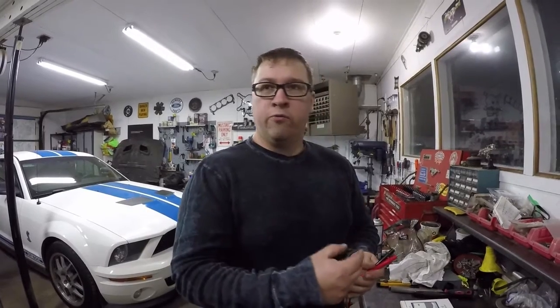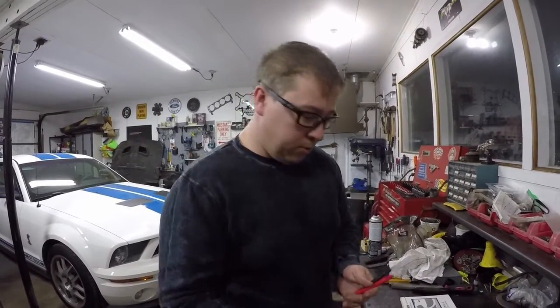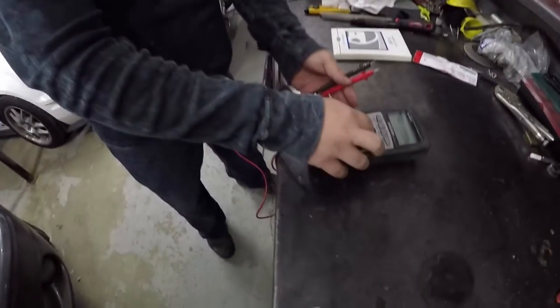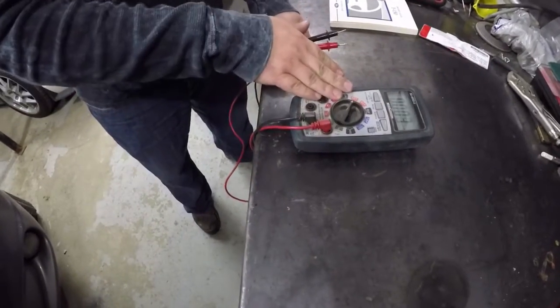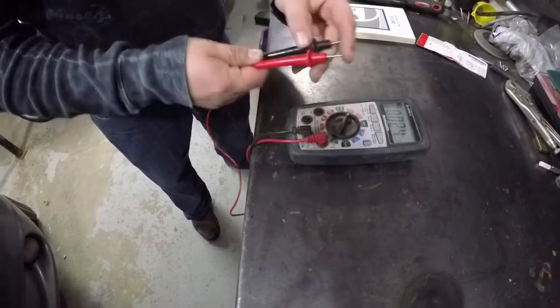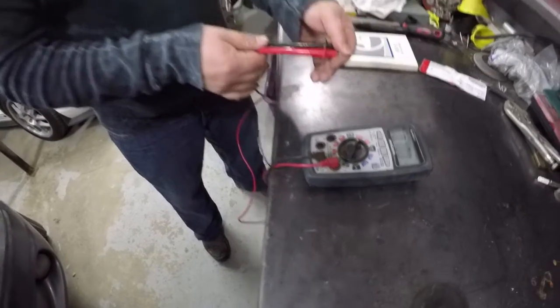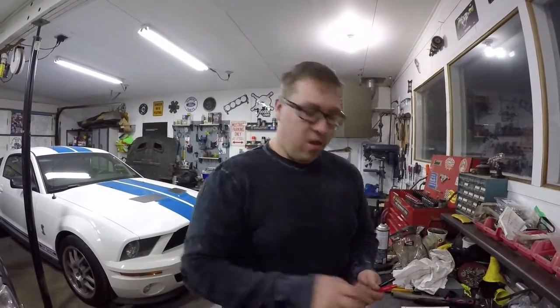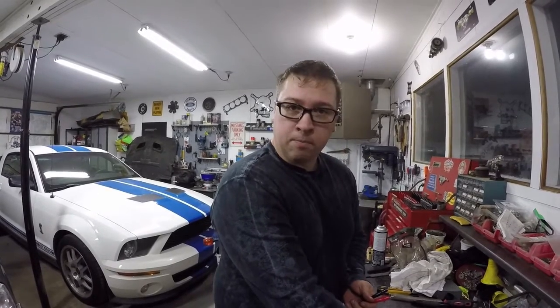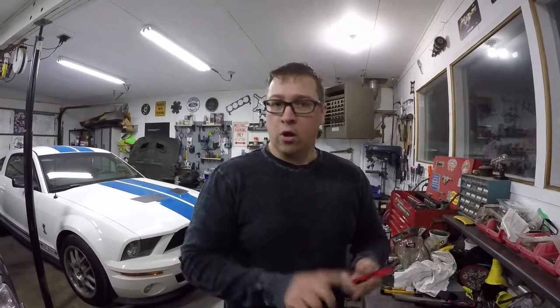And there's another way you can check beyond the fuses: check for power at the connector. So underneath the truck on the heat exchanger, remove the rear connector from the intercooler pump, grab your digital multimeter, or your analog one if you like, set it to DC volts, and connect the two probes into the female part of the connector. Have the truck running, warmed up at operating temperature, and watch for 12 volts. If you don't have any voltage there whatsoever, you either have a wiring issue, a relay problem, or double check that fuse.